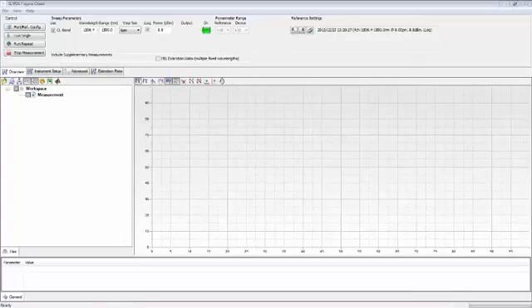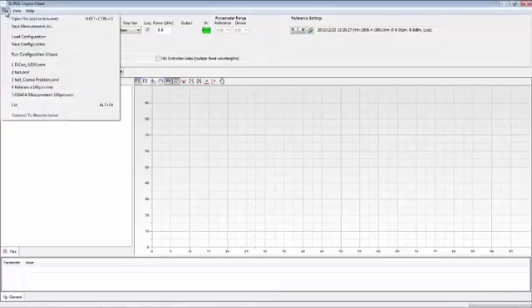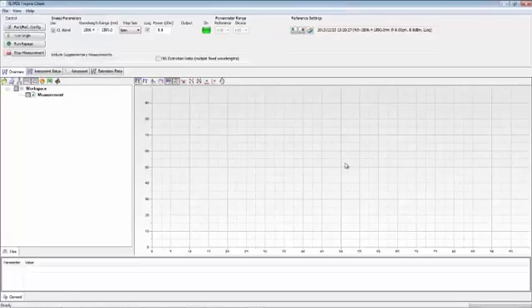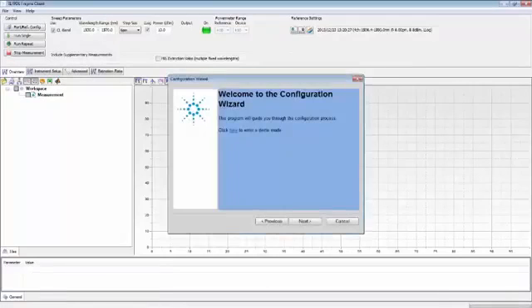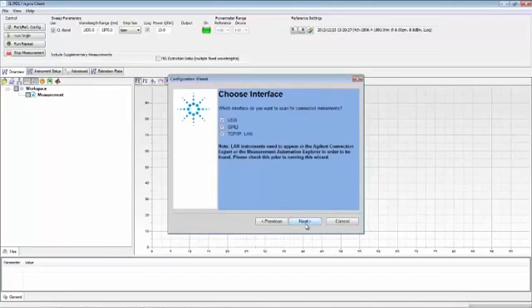We're able to connect to the instruments using the configuration wizard. This is located in the file pull-down menu and selecting run configuration wizard. The configuration wizard finds all the instruments which are currently available to make measurements. It will search for instruments over USB, GPIB, and LAN. I'm only connected over USB and GPIB, so I'll deselect LAN.